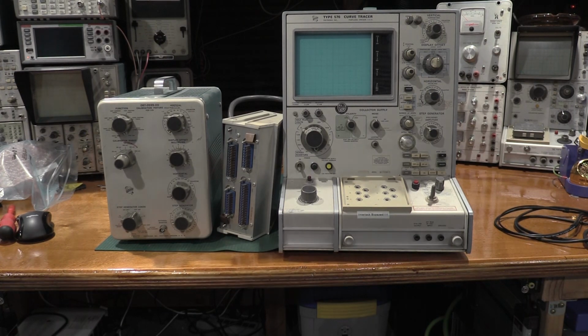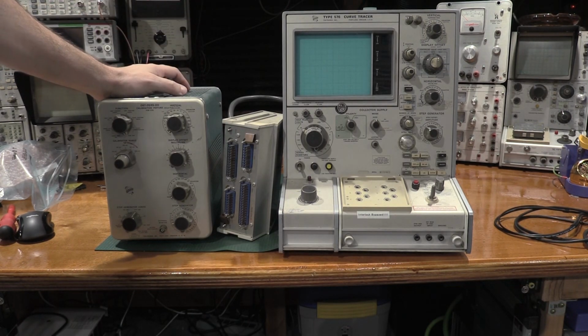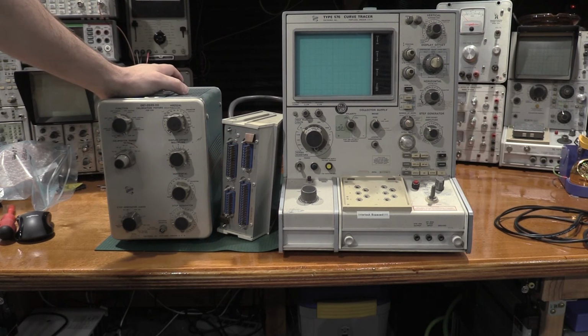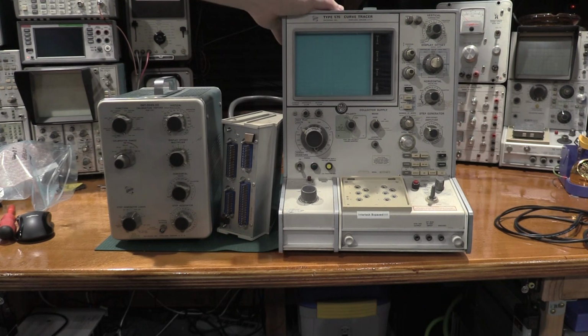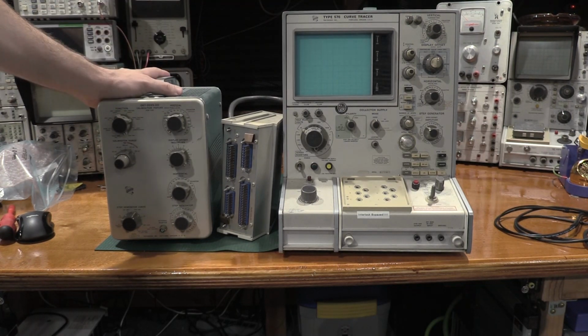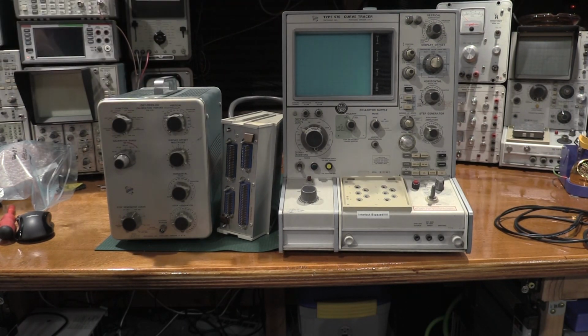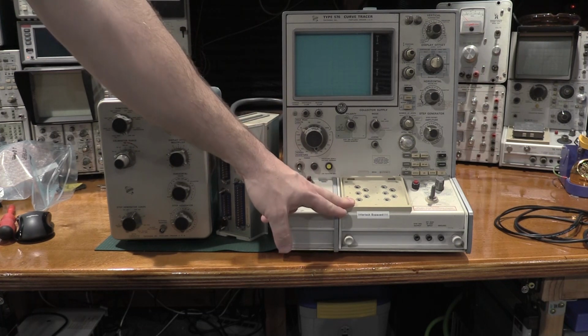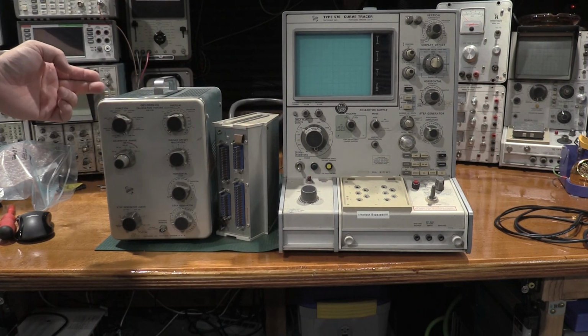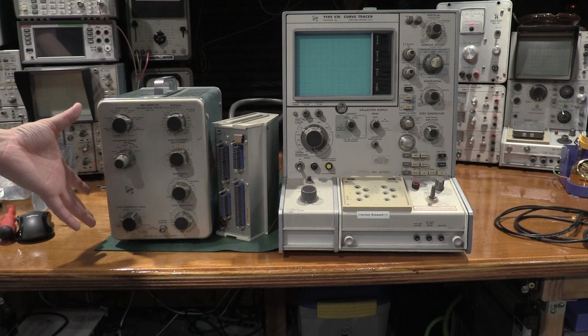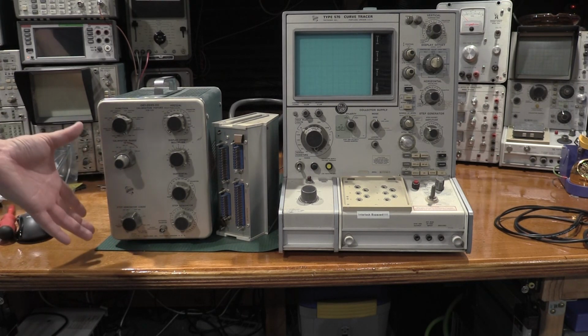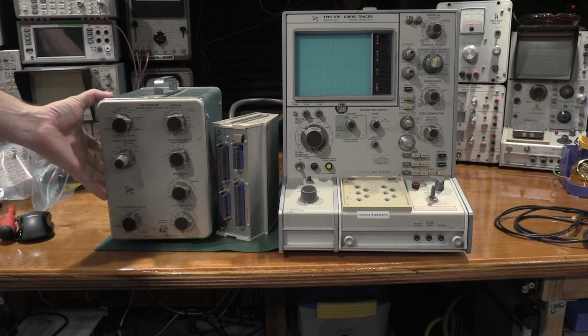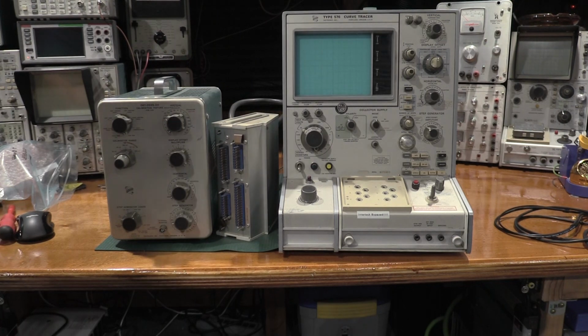A gentleman from the hive mind in the sky of the internet came up with one of these. I ended up purchasing it for him. This is the calibration fixture for a 576. There is no other use for this box other than calibrating a 576. This unit replaces the front porch, and it has all the loads and standards and capacitors and deflection ratios and things like that that you would need to calibrate the CRT on a 576.